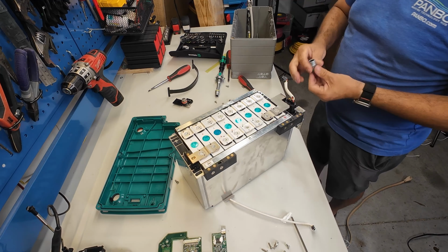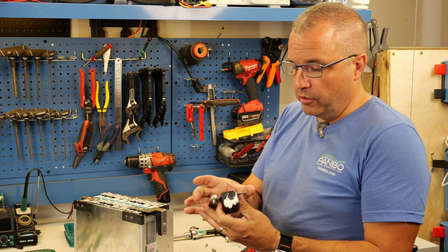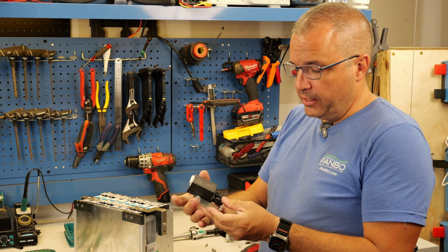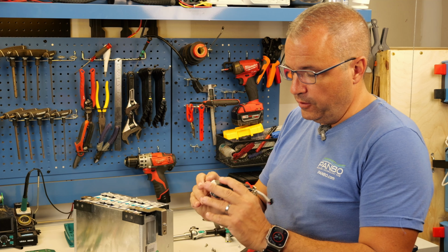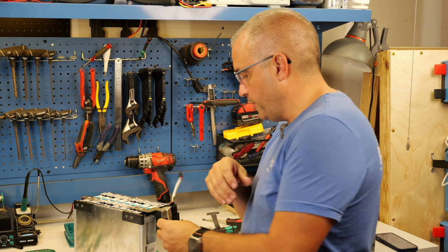The small wires coming off of it, it should be noted, are just for control of the contactor itself. There's no load running through them. The load is going to run through the larger contacts up here, which are plenty beefy, copper-plated tin-plated copper. Go ahead and put the relay back in.